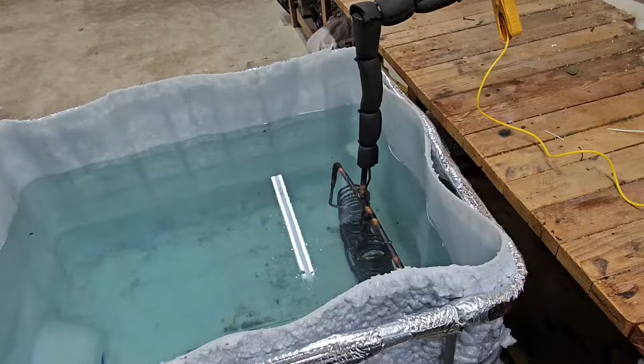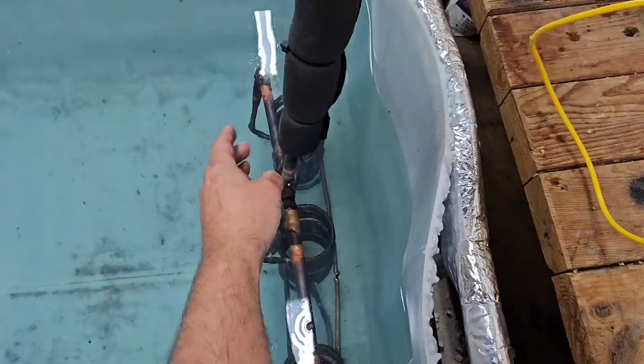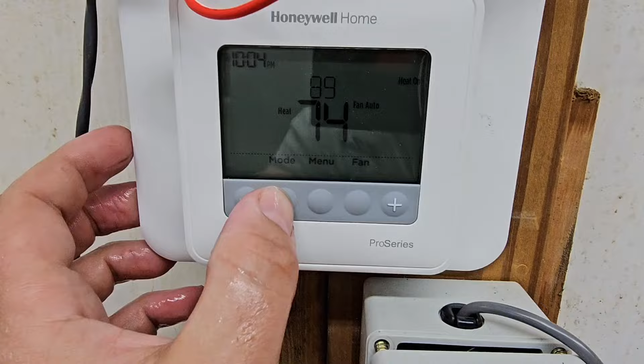Put this over here. Feel the water. Oh, it's warm. It feels good. All right, let's hook up the clamp and check the temperature of that vapor line. We've got this little temperature clamp hooked up to the meter. It's on Fahrenheit. It's 111 degrees. So this copper line is warm. Really warm. Okay, so that's the test for heating. I'm going to turn it off now.